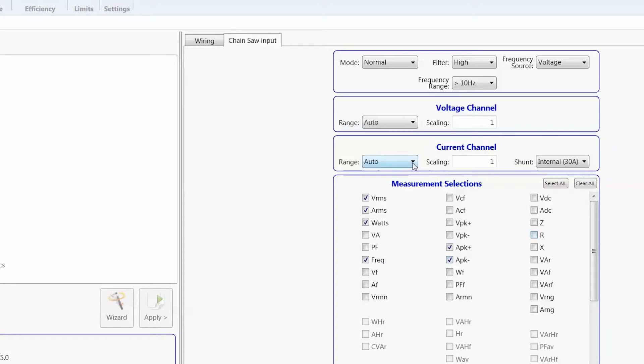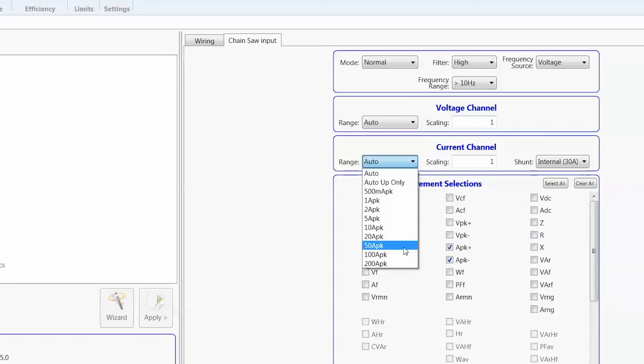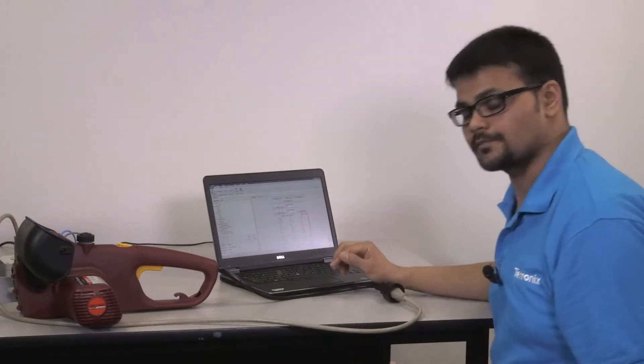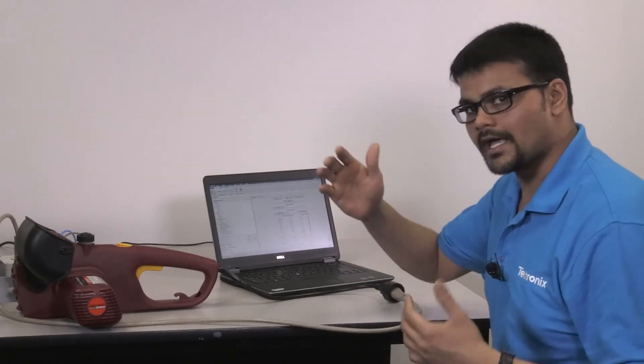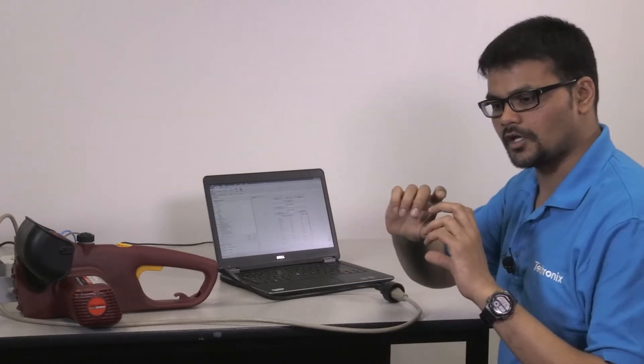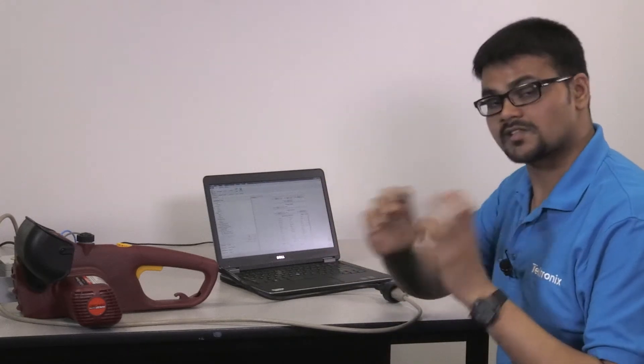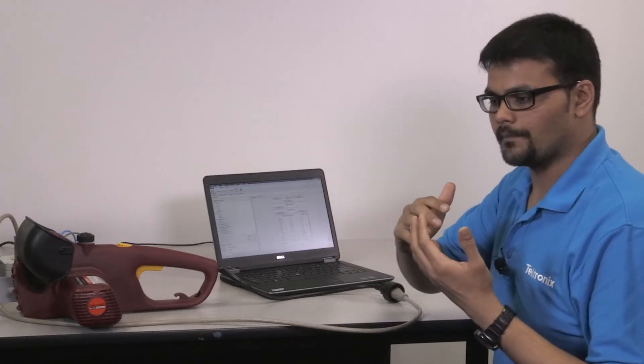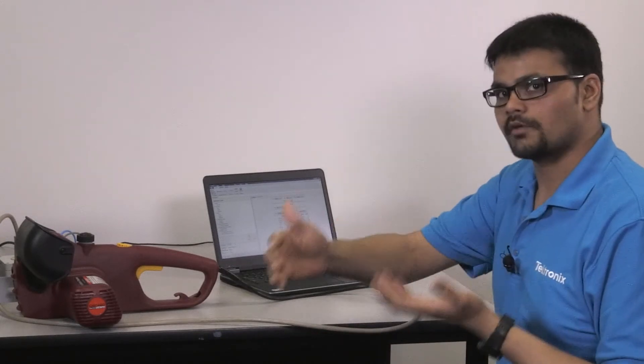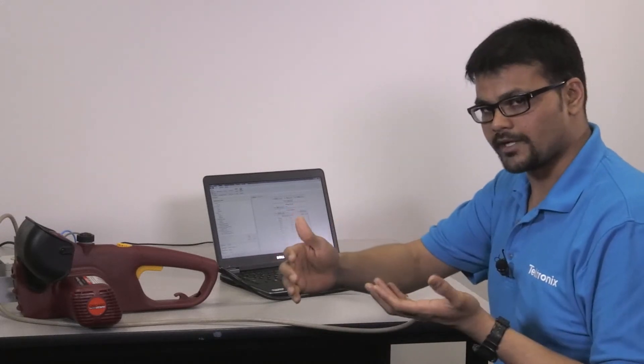And with the range, you're going to select the maximum range. Because I don't really know what the inrush current is. If it is too high and the power analyzer starts auto-ranging, it will lose the inrush current measurement.